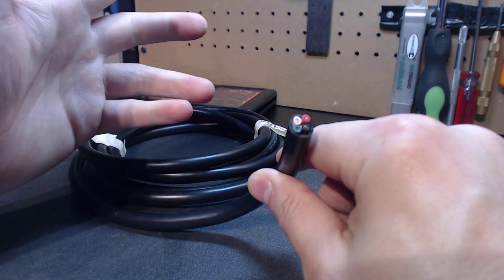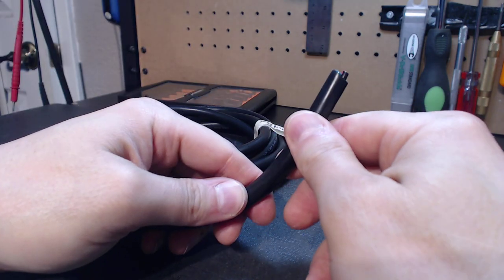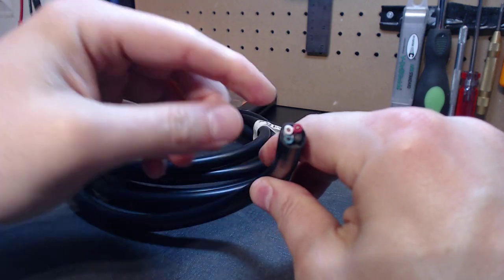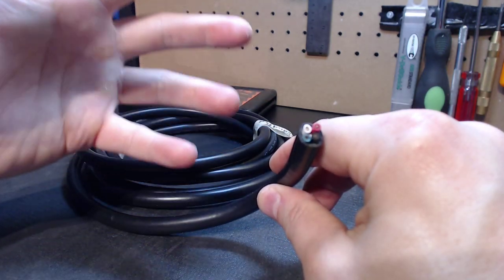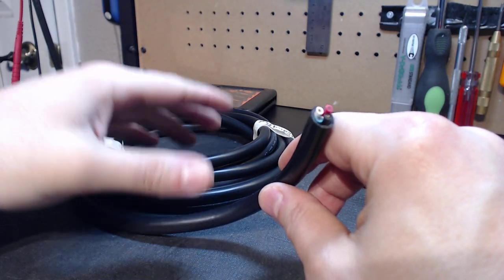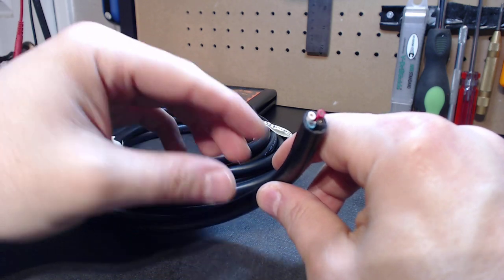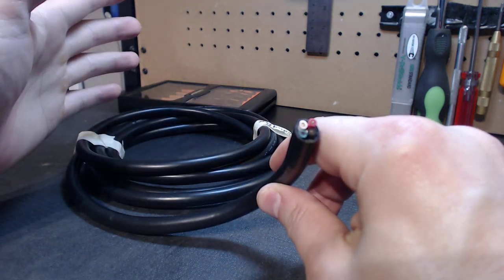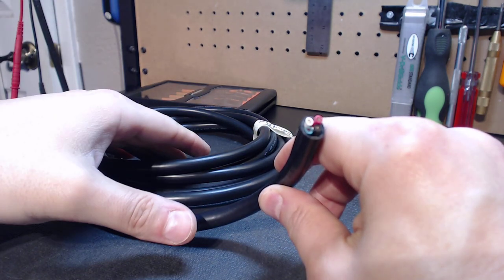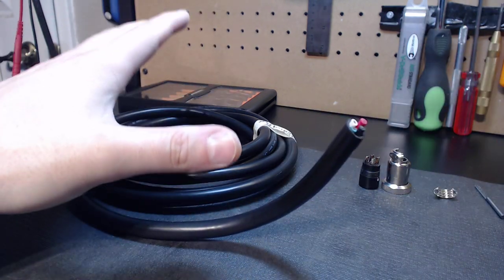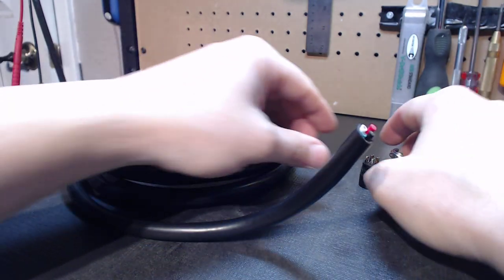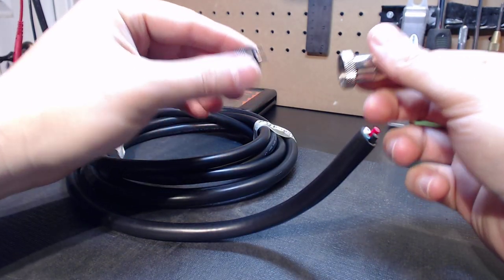Not only do you have four leads, you also have twine in between the leads. I get asked questions about that. Why is there twine in between the leads? When this cable flexes inside your cable chain, you don't want the leads to be rubbing on each other because over time, the casing will begin to fray. This is why this cable was made to my application because I know exactly what they use in full scale industry. These cables are not cheap. Double shielded cables are not cheap for a reason.